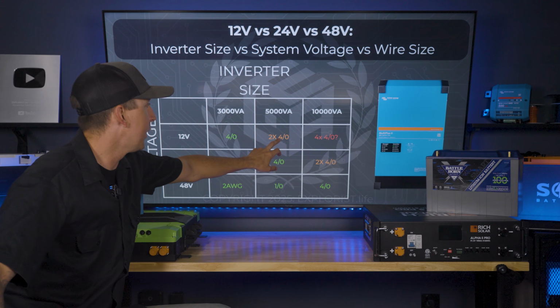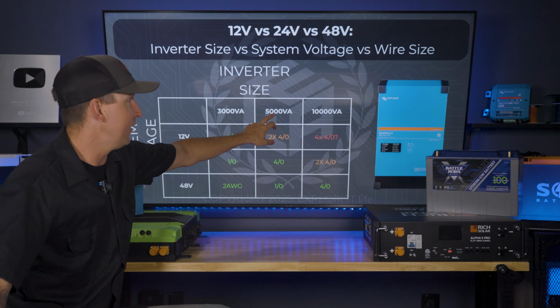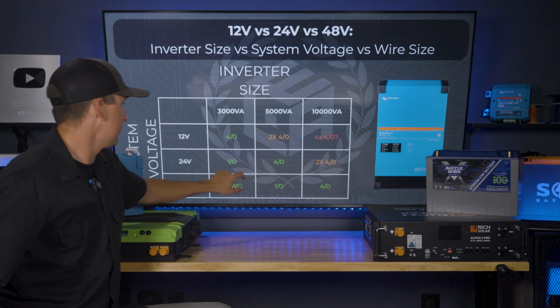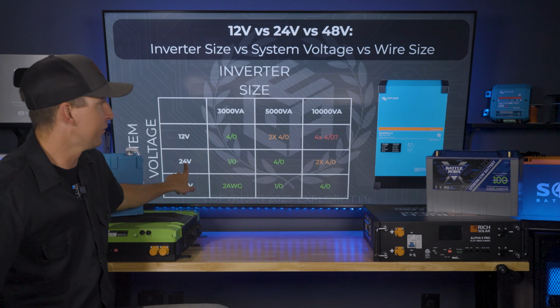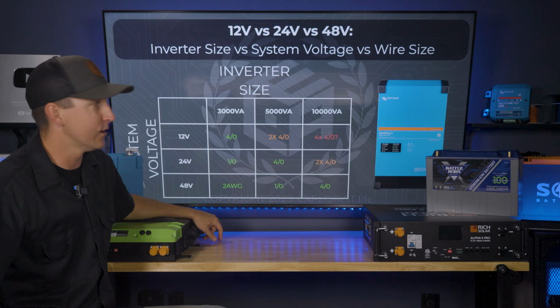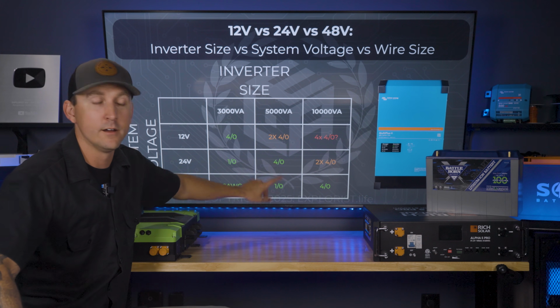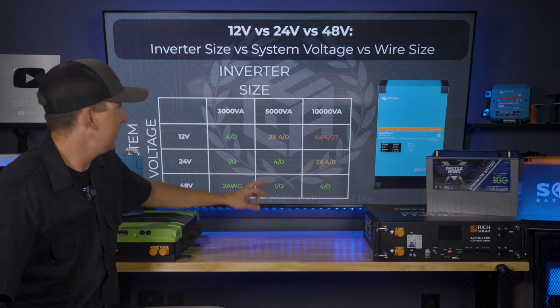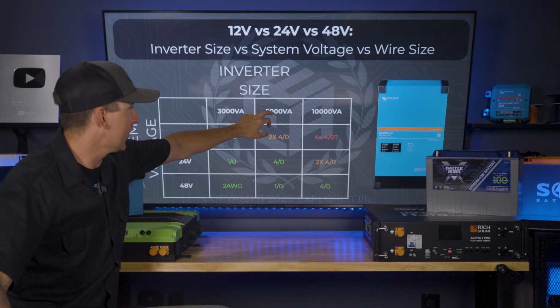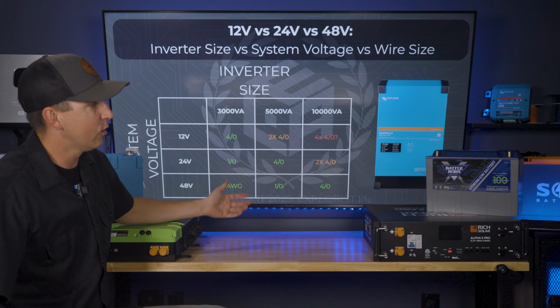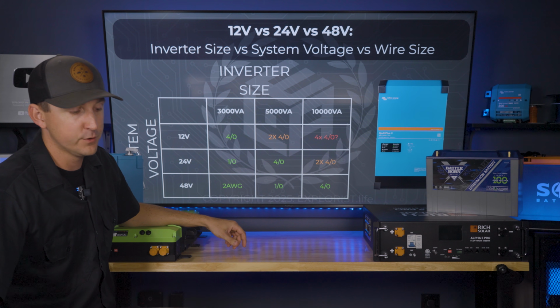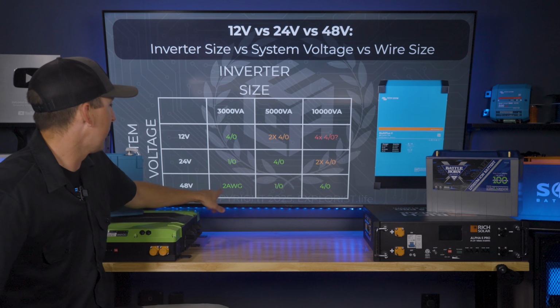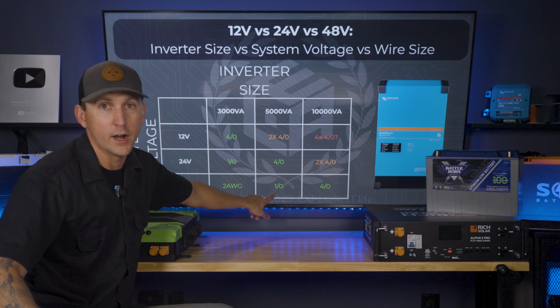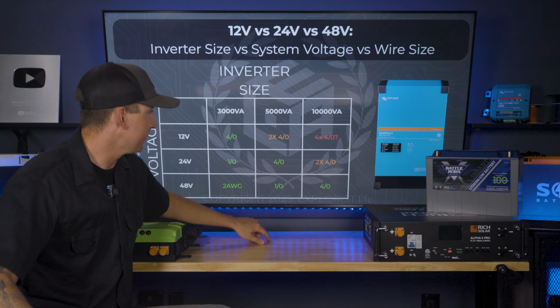So we'd opt for, if you needed 5 kVA of inverting power, to just utilize a 24 volt battery bank system so you can use that 4/0 wire. But realistically, if you needed 5 kVA of inverting power, there's not a whole lot of reason not to go with a 48 volt battery bank system, where you can use 1/0 wire, which is even smaller.